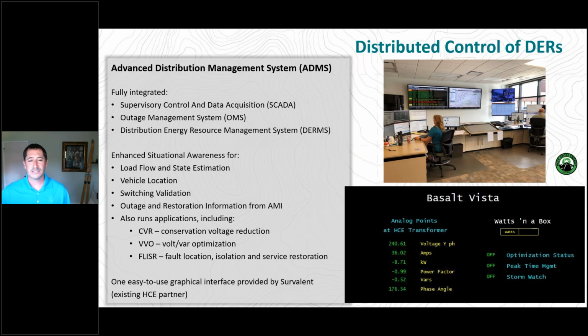From that, we designed a distribution system where we're able to put it in modes. So when we get a red flag alert in our distribution system, we change our protection scheme, making our protection open up a lot quicker so we don't create fires from fuses. This has been great for the last couple of years. This winter, we also implemented a snow watch so that when we're predicting heavy snow coming in, we can change our protection settings across our whole system to give us a better advantage battling snowstorms and outages.